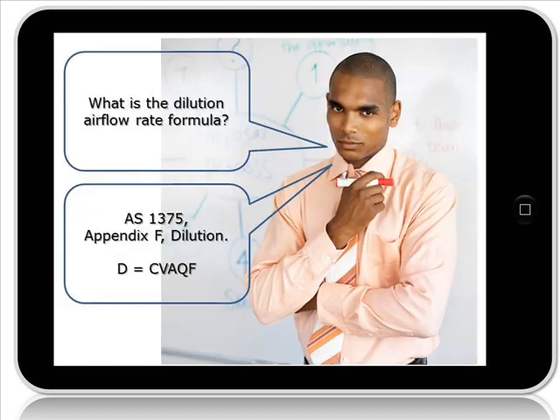Where can I find the dilution air flow rate formula? The formula can be found in AS1375 under Appendix F, called Dilution. The formula is D equals C times V times A times Q times F.